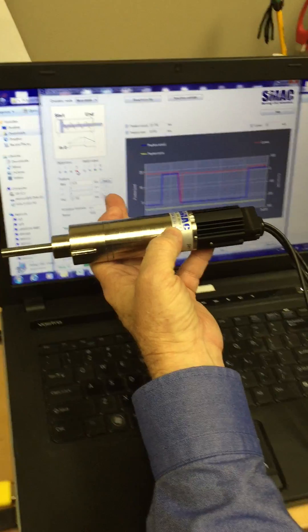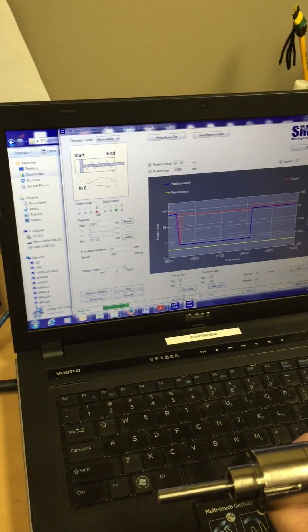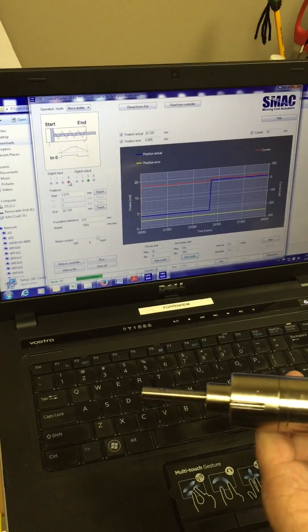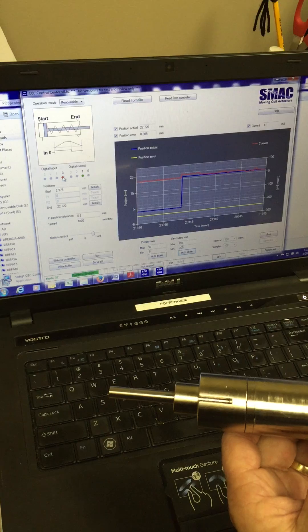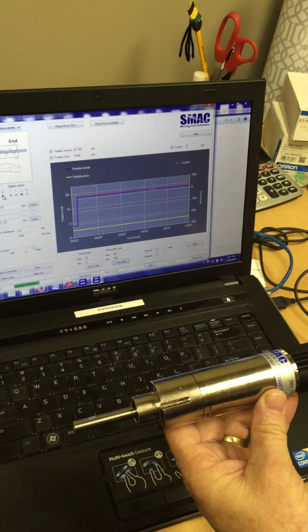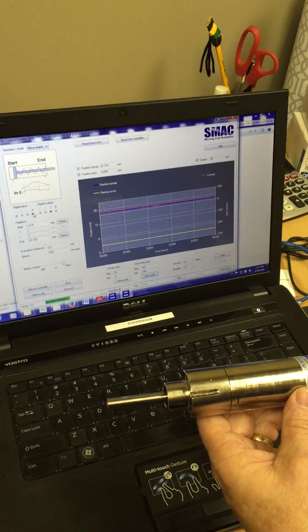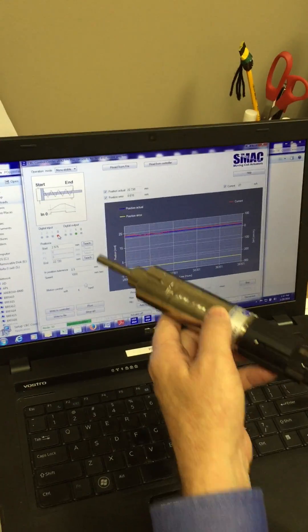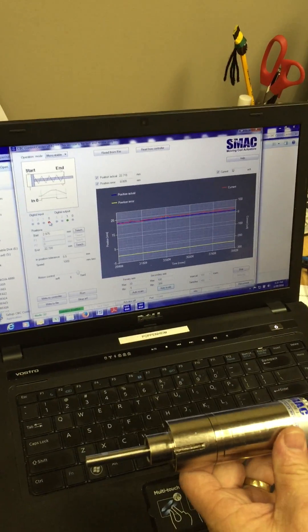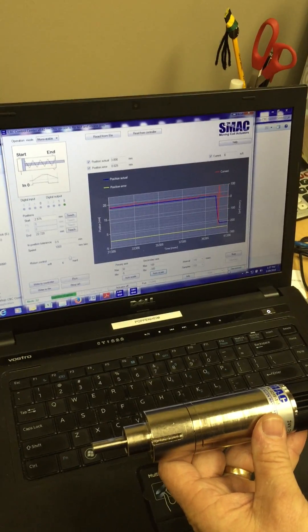And as you notice, the second output, or output number one, comes on when it's at that extend position. So now you've duplicated the same scenario as an air cylinder by applying 24 volts to energize, and you have your two end-of-stroke positions. And that's it.